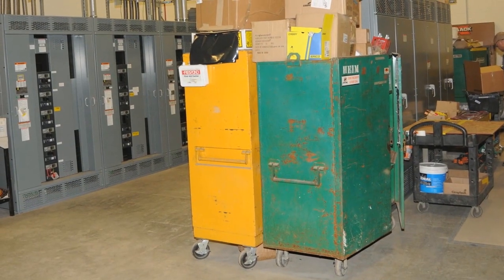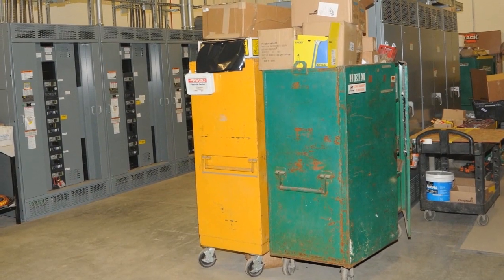Well, the purpose of that was to have dual sources in there. We have a dual feed going there. Plus also they expanded the building, where the old electric room was. It's a 4,000 amp service and there's dual services, so you can turn one service off and switch the power over to the other one and it will handle the source. Yeah, there's a tie breaker in between the two.